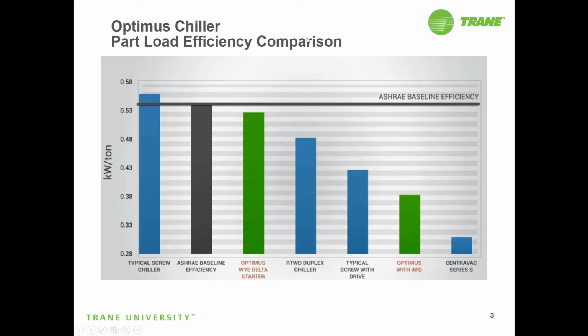Part load efficiency comparisons. So part load is the efficiency of using a drive, and with the conventional method of loading and unloading, using a slide valve covering or uncovering rotors internally, the drive adds yet another dimension of controllability for part load efficiencies. So here we're looking at part load efficiencies. Here's a typical screw chiller. You can see that their part load efficiency is a little above the ASHRAE baseline efficiency.